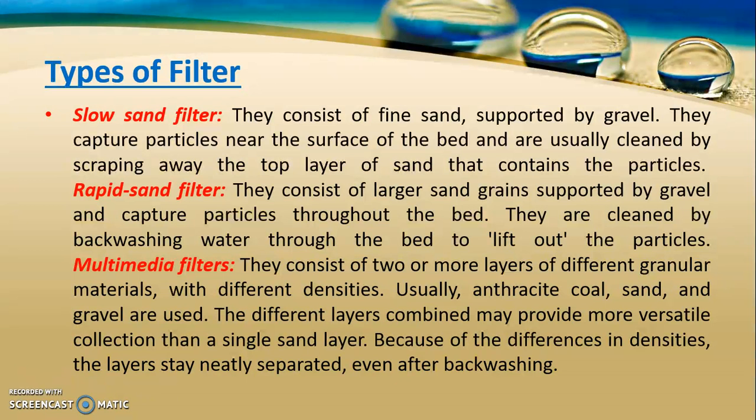Rapid sand filters are cleaned by backwashing water through the bed to lift out the particles. Multimedia filters consist of two or more layers of different granular materials with different densities — usually anthracite, coal, sand, and gravel are used. The different layers combined may provide more versatile particle collection than a single sand layer. Because of differences in densities, the layers stay neatly separated even after backwashing.